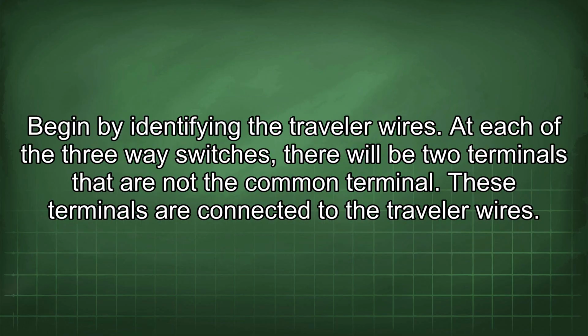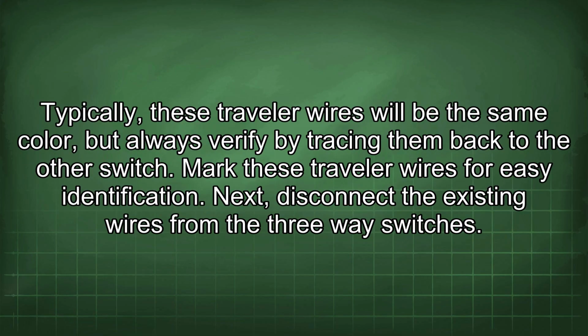Begin by identifying the traveler wires. At each of the three-way switches, there will be two terminals that are not the common terminal. These terminals are connected to the traveler wires. Typically, these traveler wires will be the same color, but always verify by tracing them back to the other switch. Mark these traveler wires for easy identification.